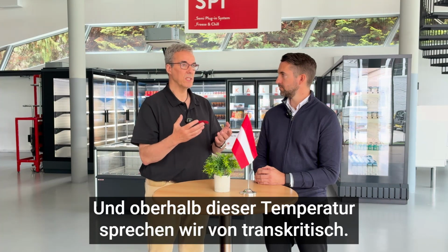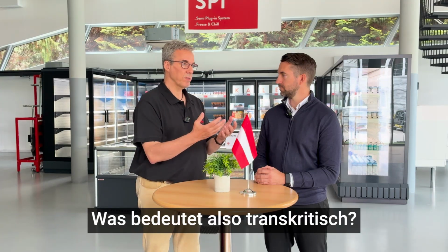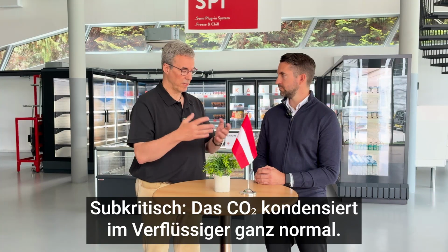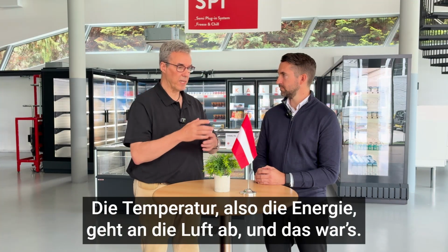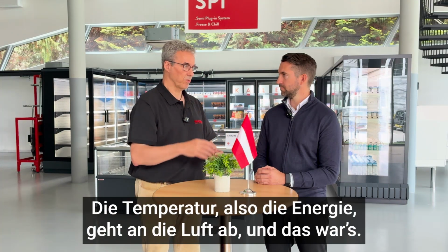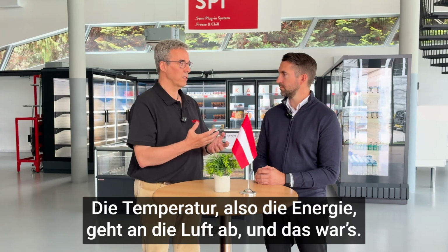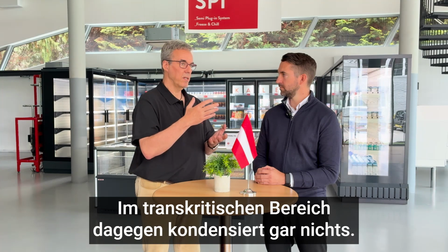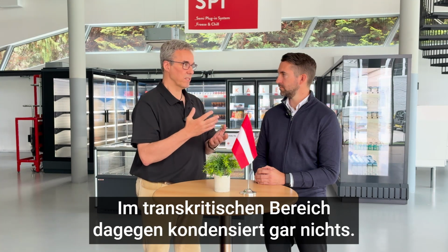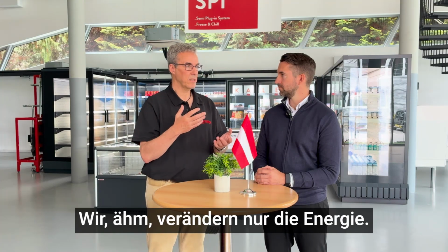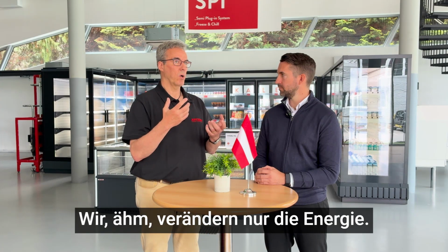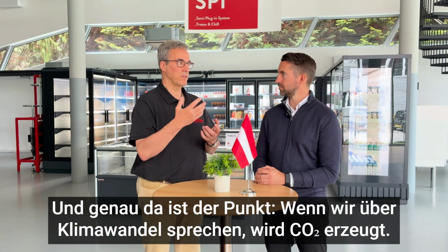So what is the meaning of transcritical? Subcritical, the CO2 in the condenser is normal condensing. Energy is going to the air, and that's it. In the transcritical point, we do not condense anything. The CO2 is not condensing. We are only changing the energy.